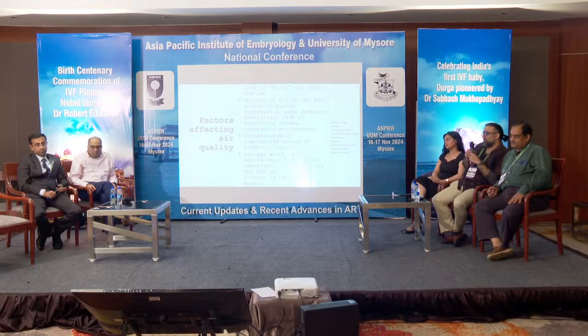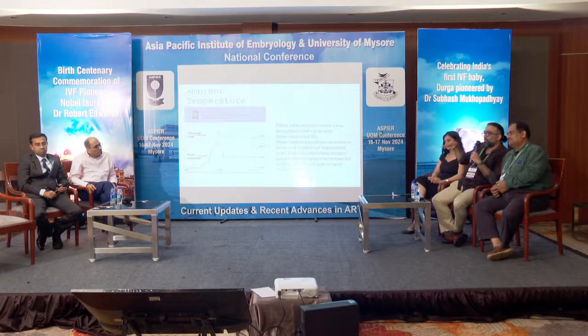And after that, all the points they have said, like you have cardboard boxes, you have plastic sleeves in which your consumables come. They should not actually come inside the lab. And then your gas as such can actually release VOCs. Suppose if you buy a new incubator, that can release VOCs. So you have to keep the incubator outside, off-gas it for a week or 10 days, then you bring the incubator inside. Generally, that is also one point where we use an AHU system, air handling unit, to do the whole thing.